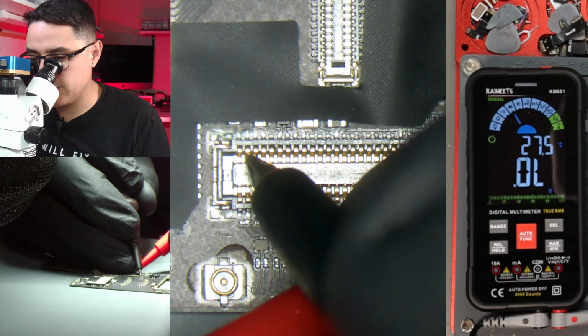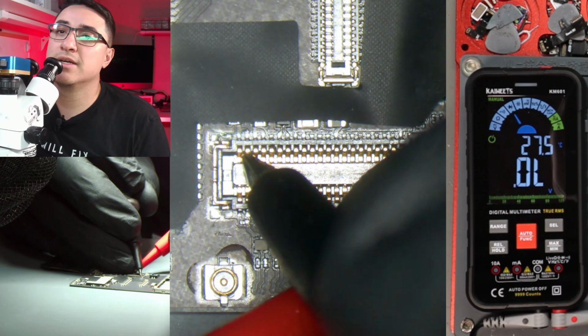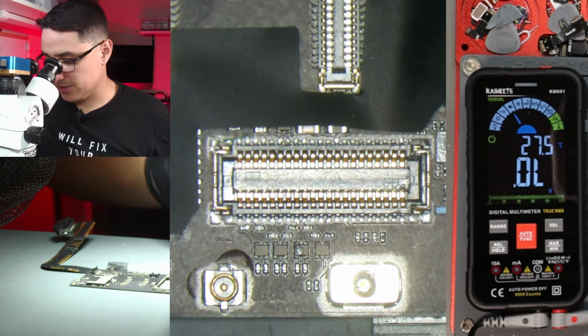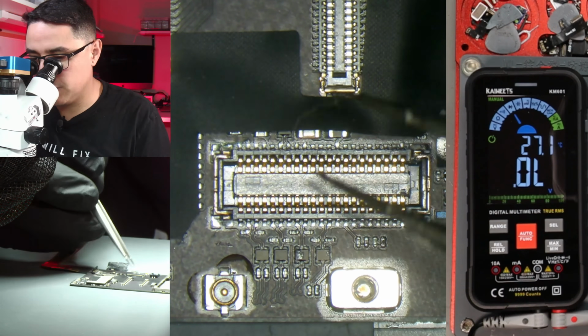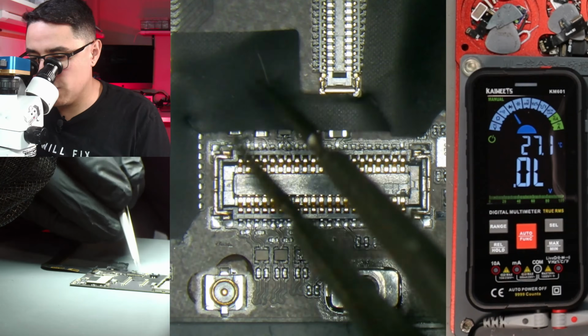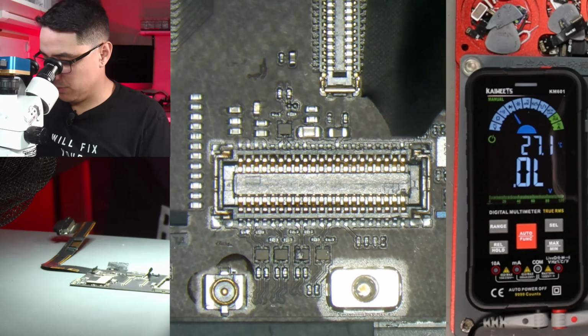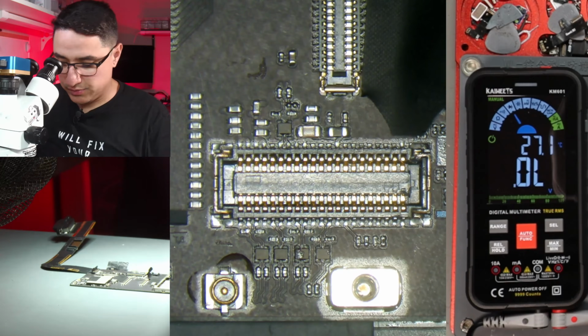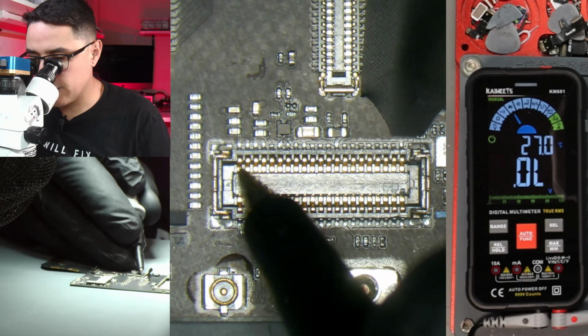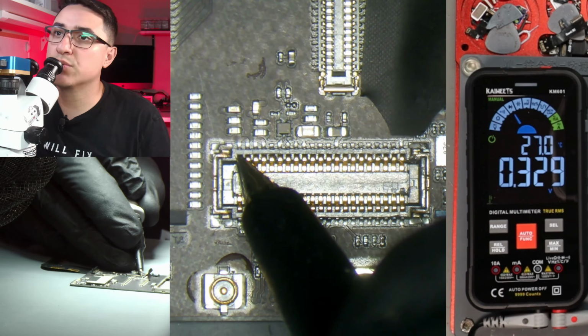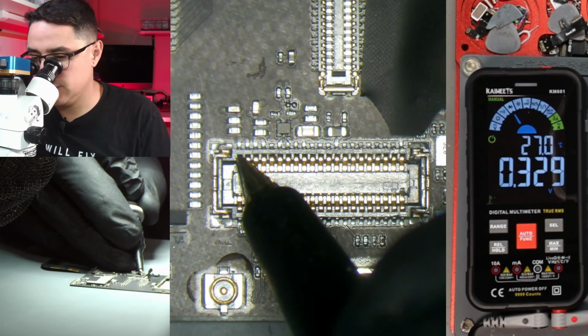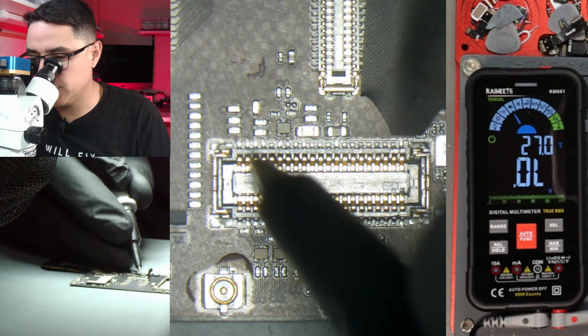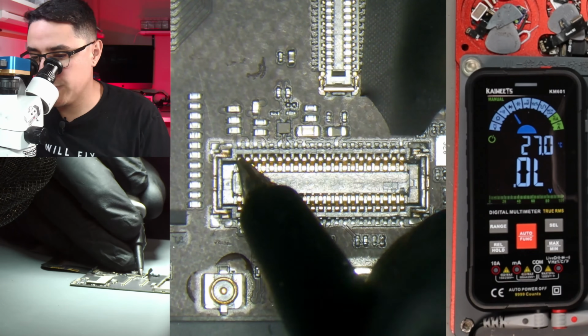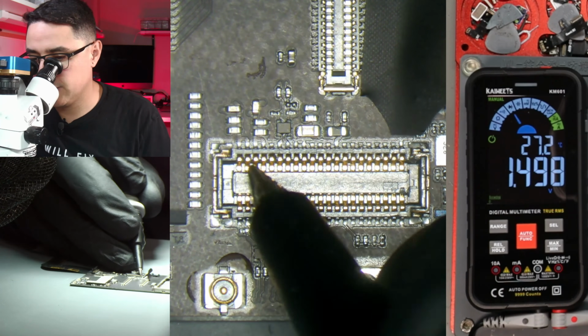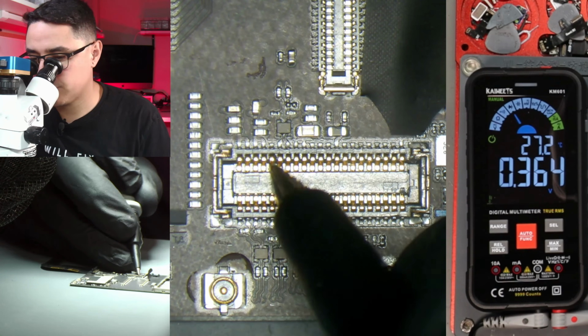So essentially, just off the top of my head, I know these are the backlight lines, and if these backlight filters that are over here blow, what will happen is, we're expecting a reading, like in this one, right? We get a reading of 0.32829. But if that backlight filter here was blown or damaged or missing, we would get OL, but we get a reading. And the same over here.